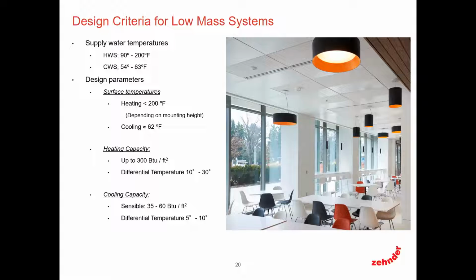And the reason it depends is how these panels are installed. If the panels are installed in a closed ceiling like this, like a standard lay-in grid application, that is going to be one performance. If they have insulation on the back, that would then generate a different performance. If these are open to structure with or without insulation, that will generate a second or third different kind of performance. So where I'm going with this is it's important to understand what you're integrating these panels into, because that will drive the BTUs per square foot of the panel.